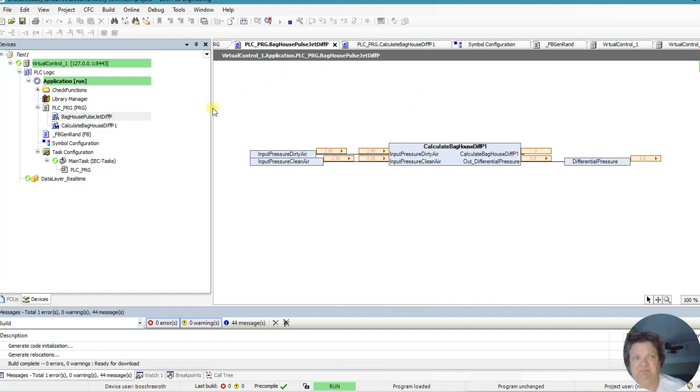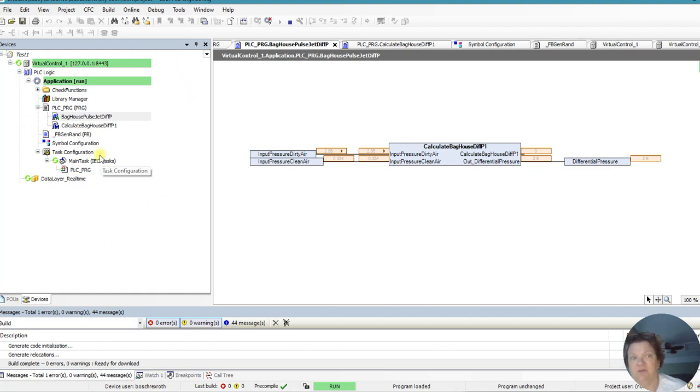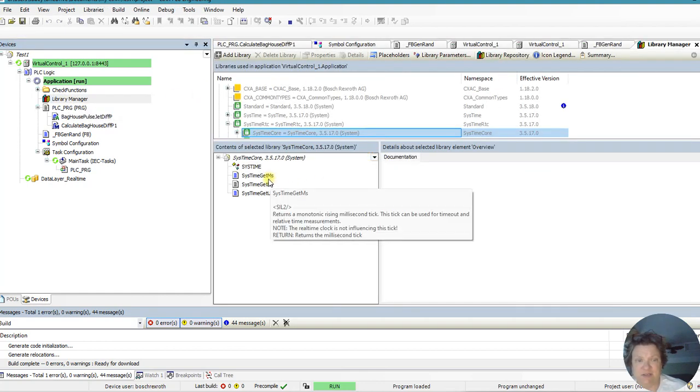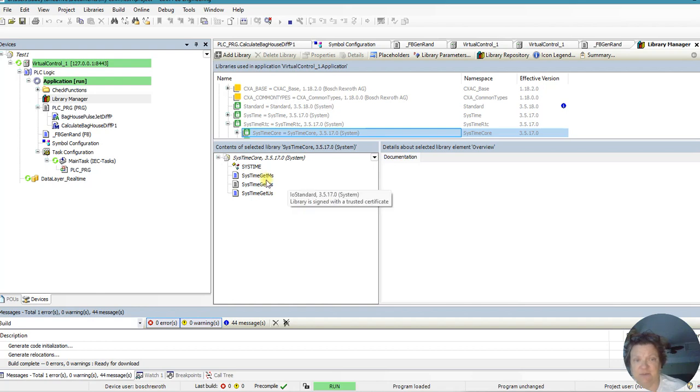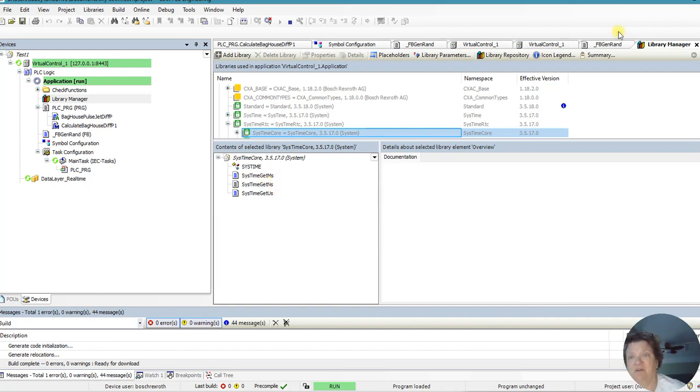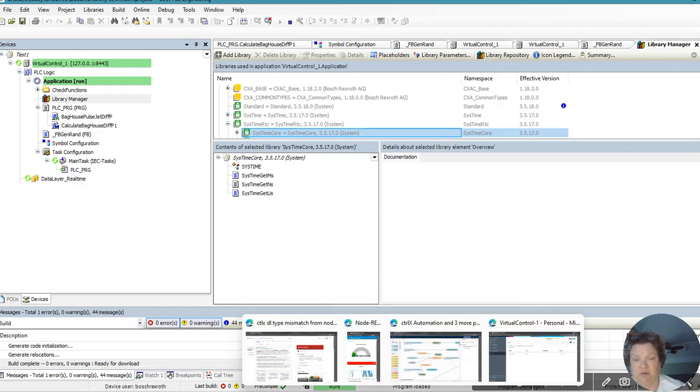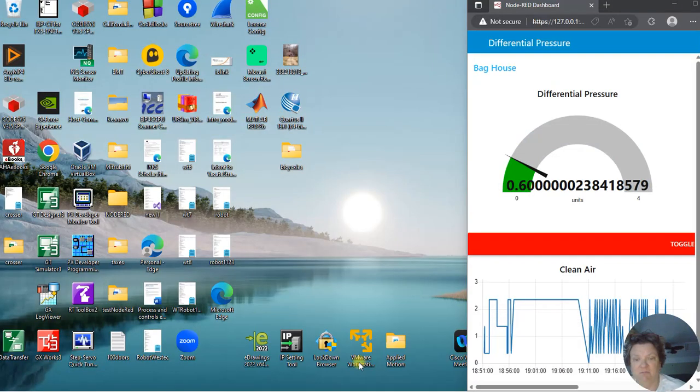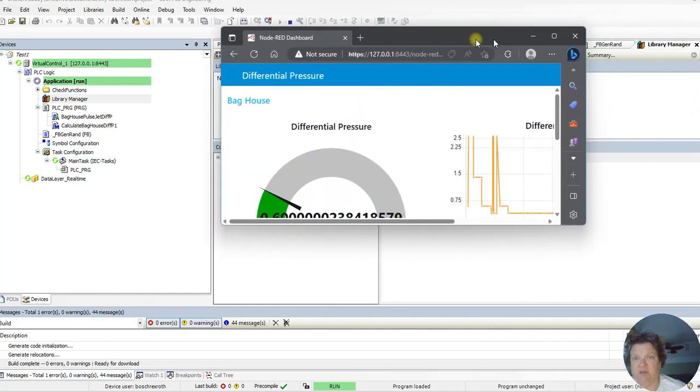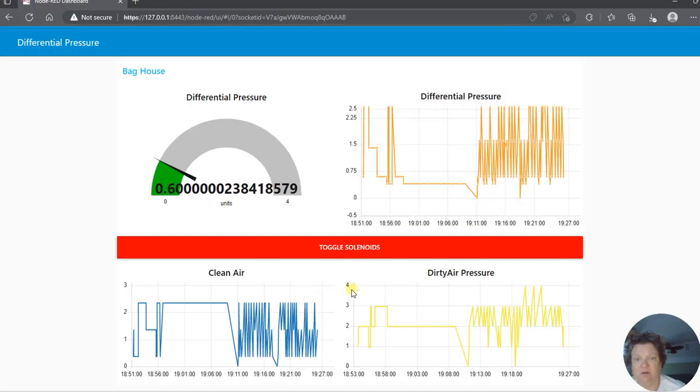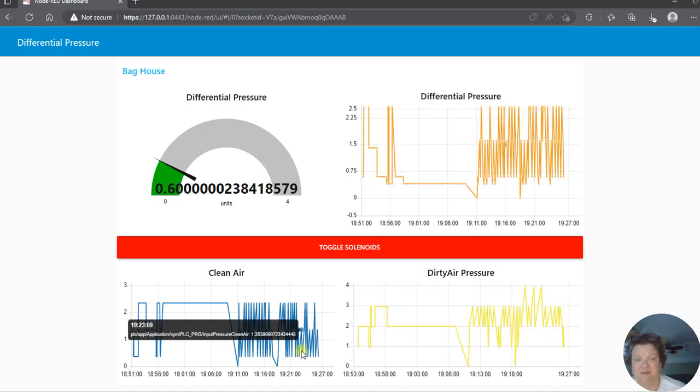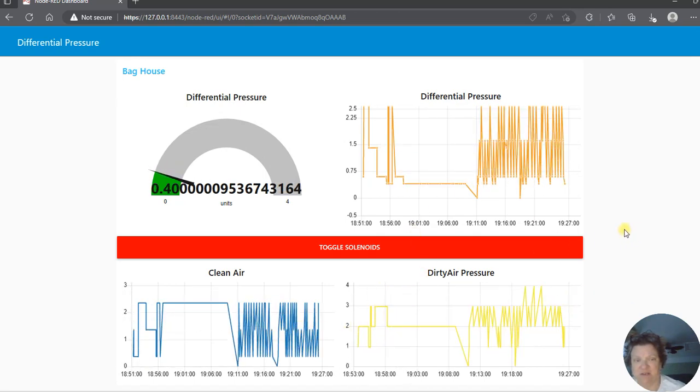And that's the other thing. If you keep your calculations and your manipulations at a lower level, so the PLC program is here, this is more like a higher level for the action and the calculation is down below. Again, if you get in the habit of programming in such a way that people can't get to your calculations and your PIDs and the meat and potatoes of the control, if you hide it below or above in the stack with the functions, then you can protect yourself even if somebody got on the PLCs. And then also it's just repeatability and modularity for good programming practice. Which is Codesys oriented for people that aren't familiar with Codesys. And this is a Codesys platform, so there's quite a bit that you can do.